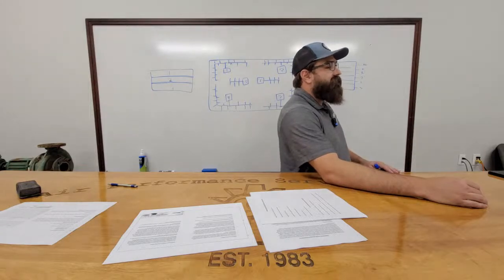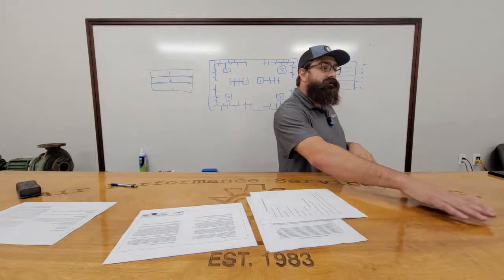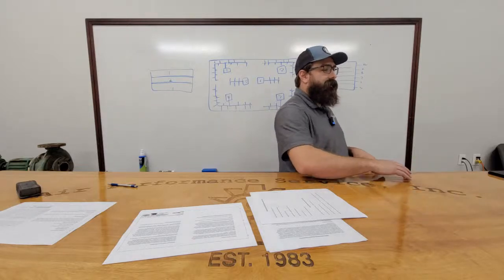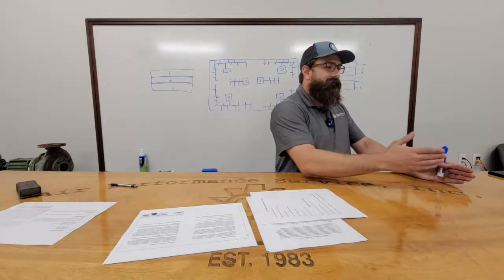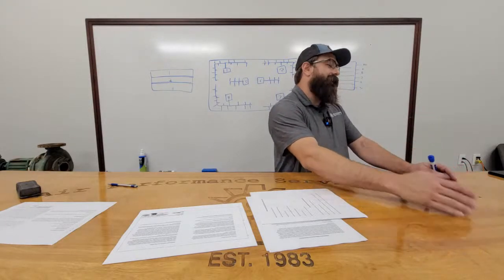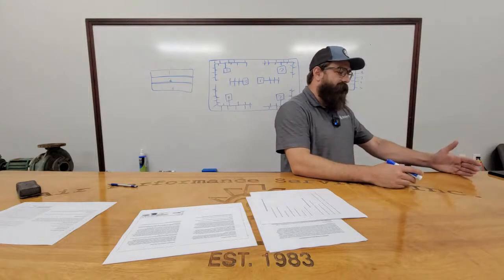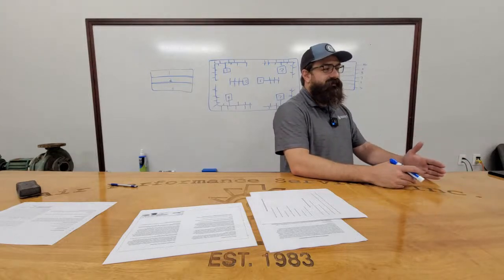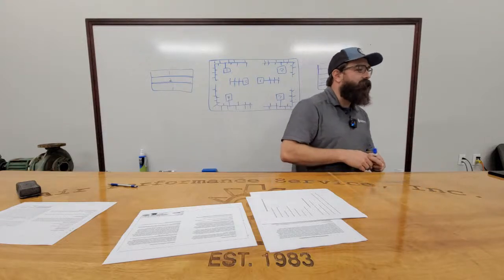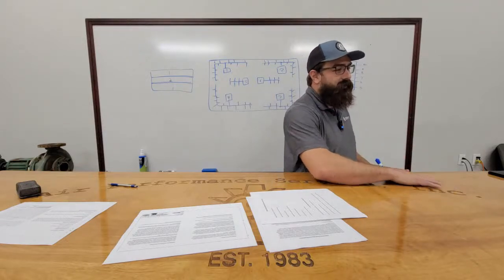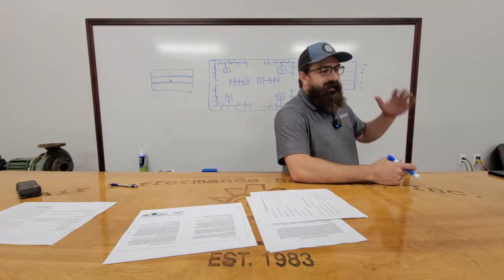Optimized start stop doesn't need it because it's not a true PID algorithm, right? It's not a proportional output. If I had 100 units and I wanted to start them at a certain speed, then I could use a PID. But this is more of, hey, if outside air temp is this much, we want to start the schedule at this time. It's a lot more basic program than a PID algorithm, because a PID is proportional. This only has like five different steps or something like that.